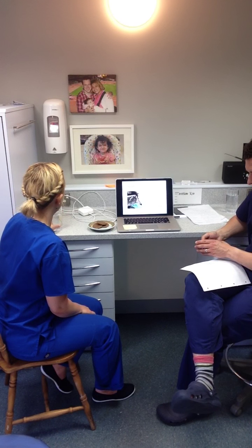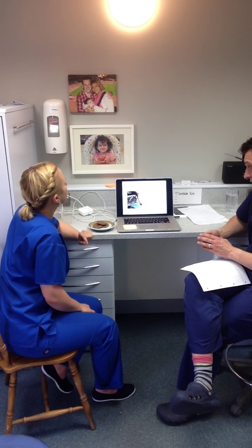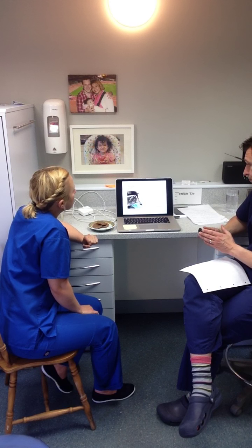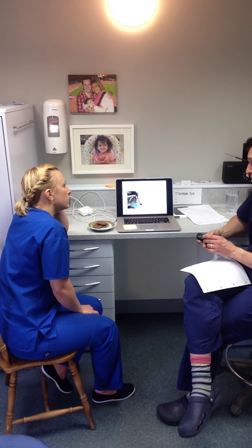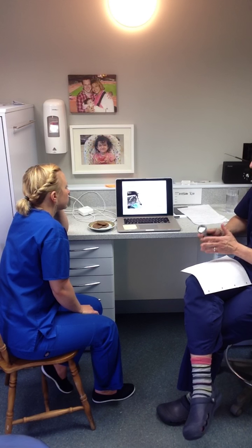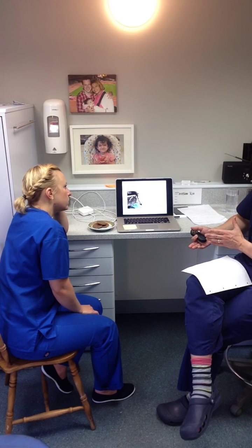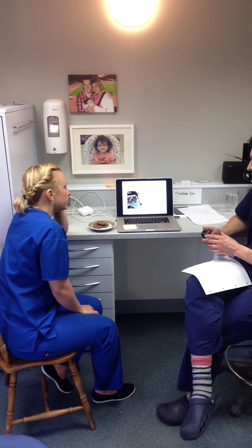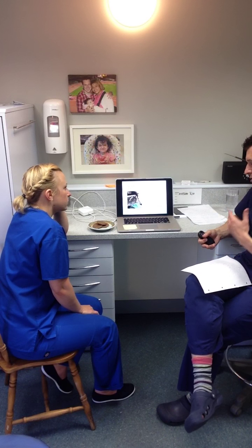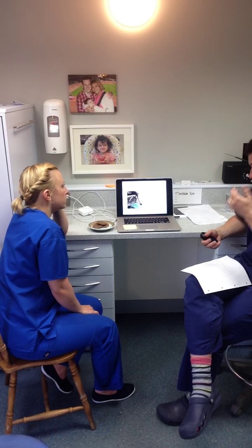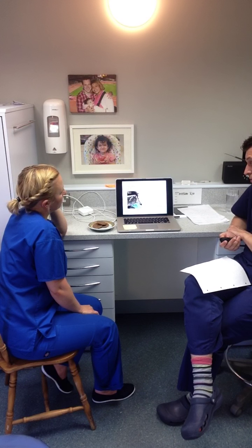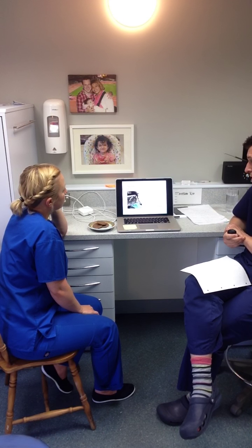So the key features of essential practice are that there should be a validated decontamination process. I've got to admit, within the decontamination process that we use in practice, there's only really the sterilisation that you can actually validate, and we're currently looking at trying to improve that on the back of the dental foundation training inspection. At the end of the process, the instrument should be sterilised, and that should be consistent for every load that you're putting on.